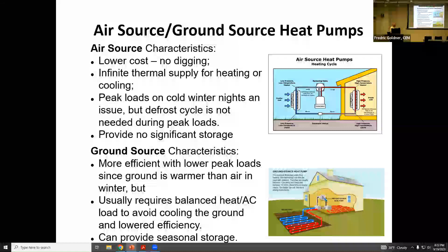So air source heat pumps have a couple of other issues. The biggest one is that with the popular mini splits, which are ductless air source heat pumps, they require refrigerant tubing going all through the apartment or the building or wherever. And the refrigerant tubing is put together with compression fittings, which are the same things that are used for copper tubing and propane and gas systems and so on. And these are hard to make up. I can vouch for that. I've had to work on them for many minutes to get a leak-proof joint.